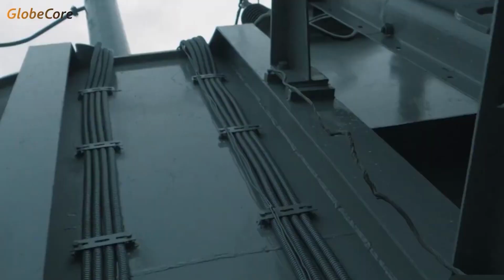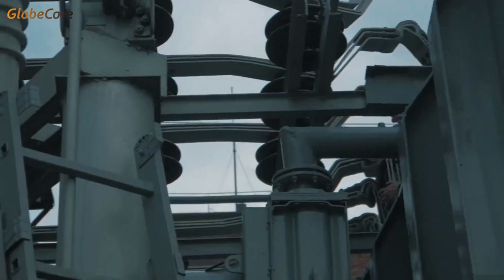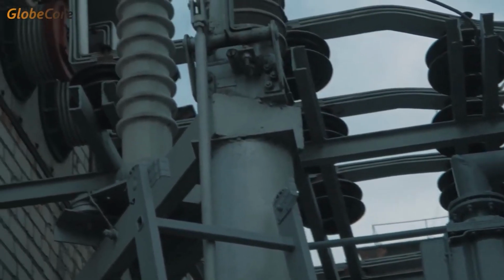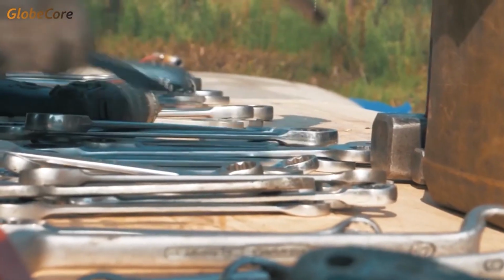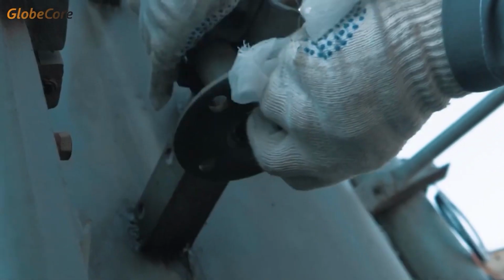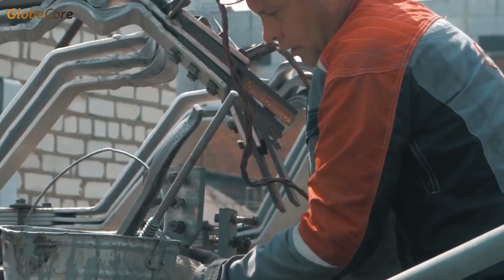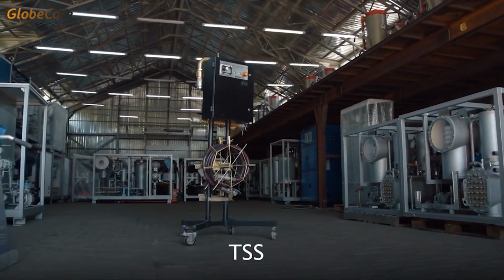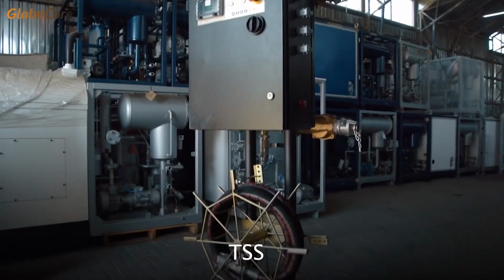For the first time, Globecore offers a solution for oil purification, regeneration and degassing on an energized transformer. Now there is no need to disconnect a transformer from the grid and sustain idle time losses. TSS allows a customer to fulfill routine servicing on a transformer online.